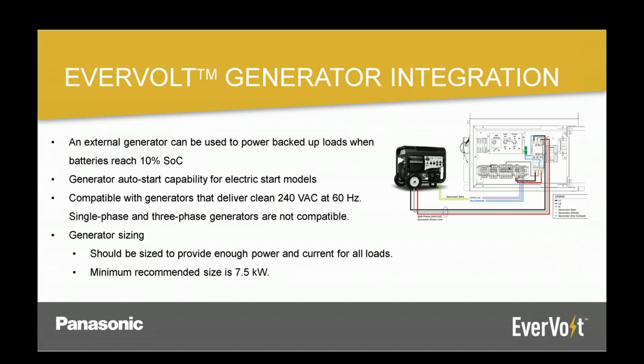Now, something that's fairly unique with EverVolt is that we do have generator integration. What this means is that if somebody has a concern that they need days of autonomy, or they're concerned that they're going to drain their battery bank too quickly, or they're going to need more power, and either they already have a generator or they can buy a fairly cheap generator on top of it, the way it works with EverVolt is two ways. One is we can integrate directly with our inverter. So when the batteries reach a 10% state of charge, we can auto start that generator and it will take over and power the loads until PV comes on the next day or the grid comes back.